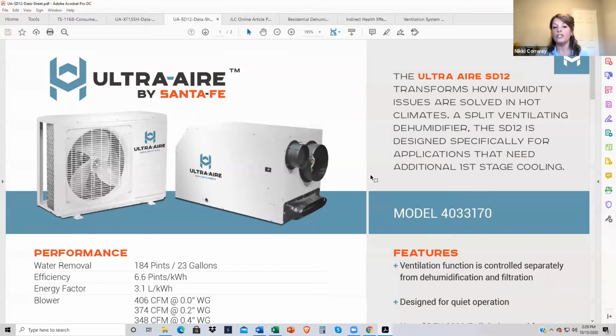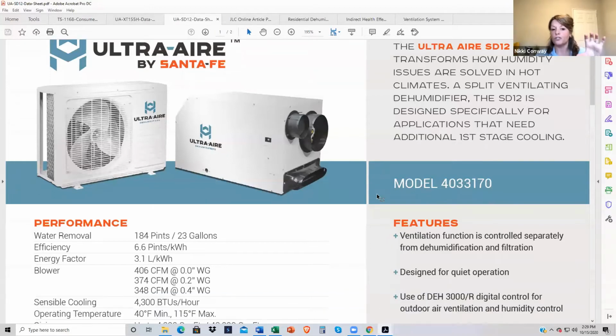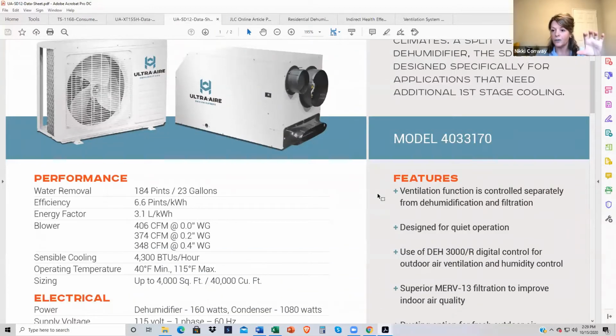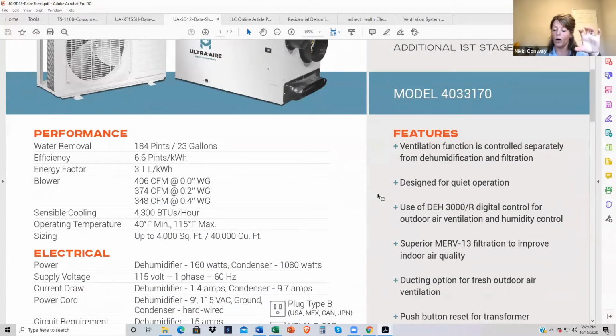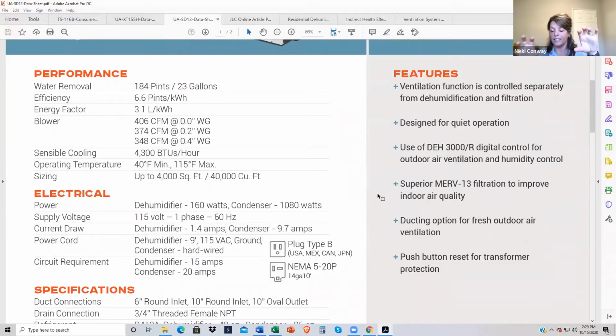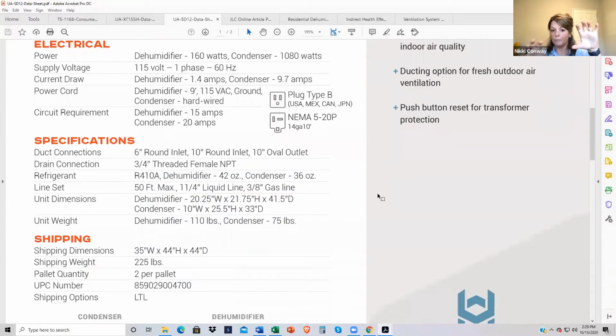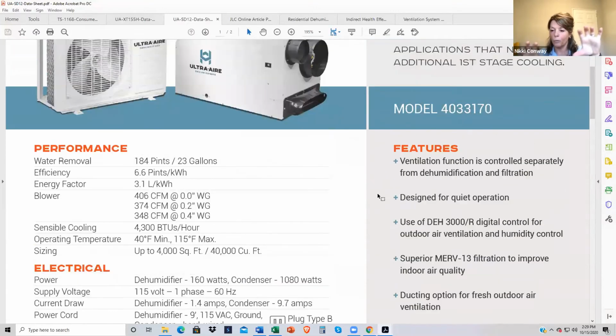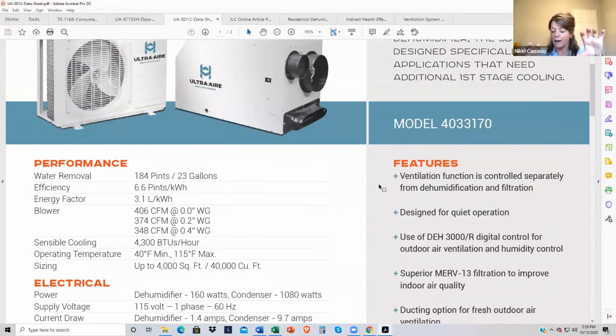So this unit is about 70% latent, or water focused, removing water, and 30% sensible, getting to that temperature. Whereas an air conditioner is designed to be 70% typically sensible and 30% latent in our more traditional units. I'm not talking really high efficiency units by any means.